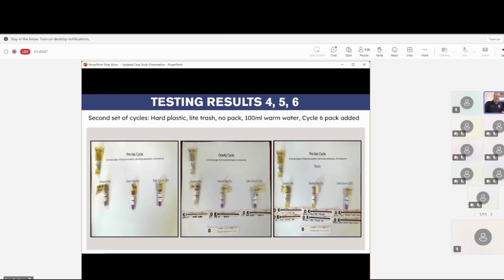And then take it one more beyond that. For 4, 5, and 6, what I did is on the pre-vac cycle, this was the last one that I started putting trash in it. I did not use the tie wraps. It was still with tape. Unremarkable, we got the kill. The bags were opening up and getting in. You'll notice here when we get to cycle number 5, and again, this is with just hard plastic and 5% trash, look what happened on the gravity cycle. The bag remained intact on this one, is what happened.